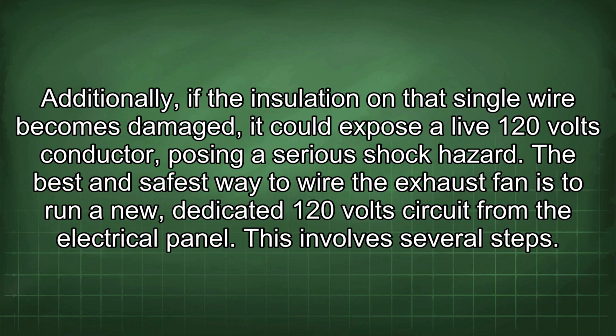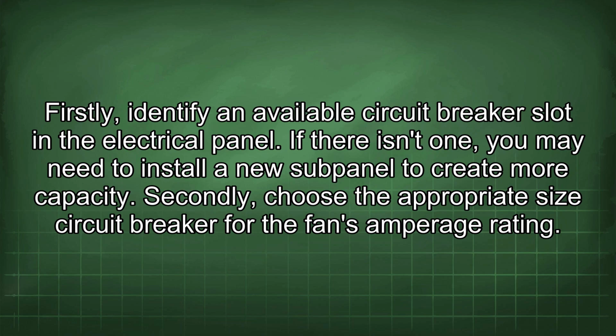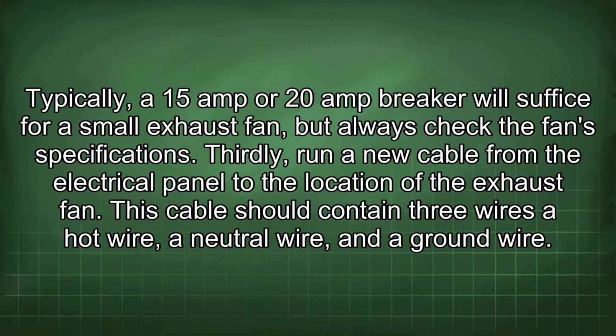The best and safest way to wire the exhaust fan is to run a new, dedicated 120 volt circuit from the electrical panel. This involves several steps. Firstly, identify an available circuit breaker slot in the electrical panel. If there isn't one, you may need to install a new subpanel to create more capacity. Secondly, choose the appropriate size circuit breaker for the fan's amperage rating. Typically, a 15 amp or 20 amp breaker will suffice for a small exhaust fan, but always check the fan specifications. Thirdly, run a new cable from the electrical panel to the location of the exhaust fan.